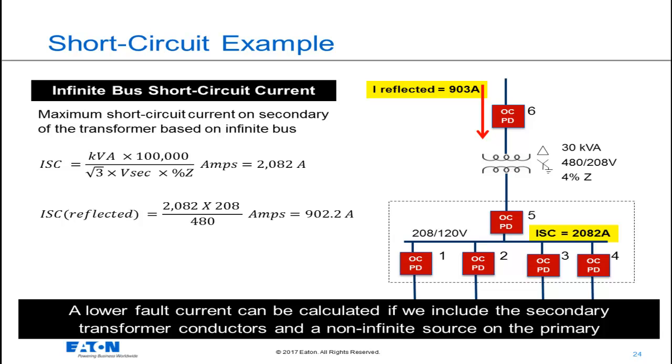This could reduce the available short-circuit current at the secondary panel, but will depend upon the size of the conductor and the length of that conductor. We're also omitting the fact that we will not have an infinite bus on the primary. We will probably be starting with some lower level of short-circuit current at the primary of the transformer. But these omissions may, in reality, be insignificant to the process that we'll be following.